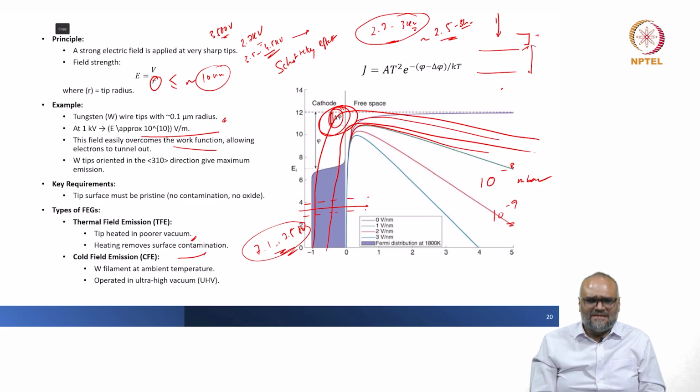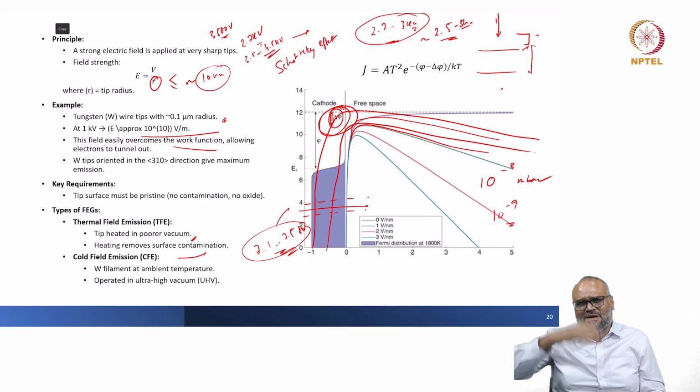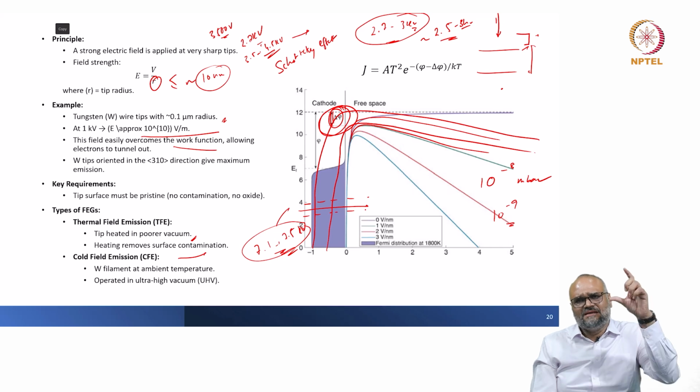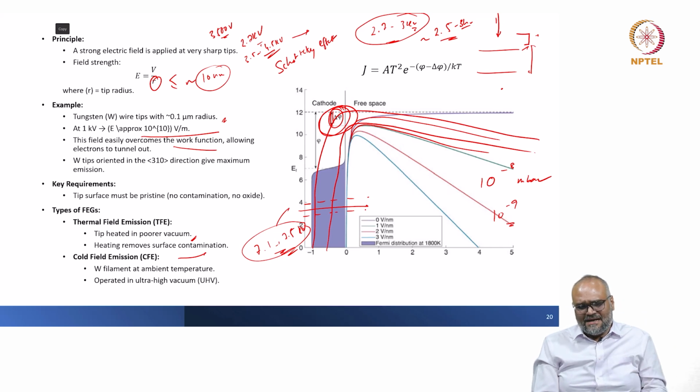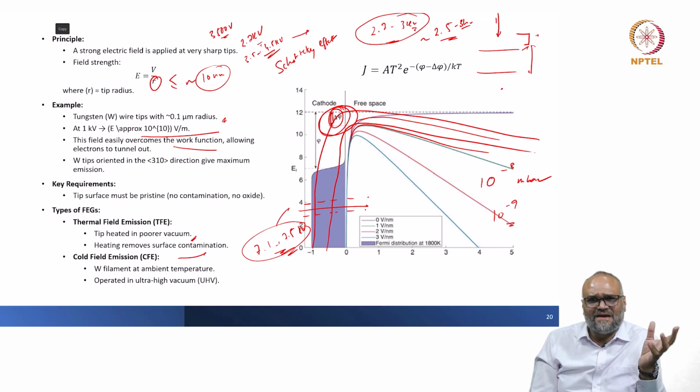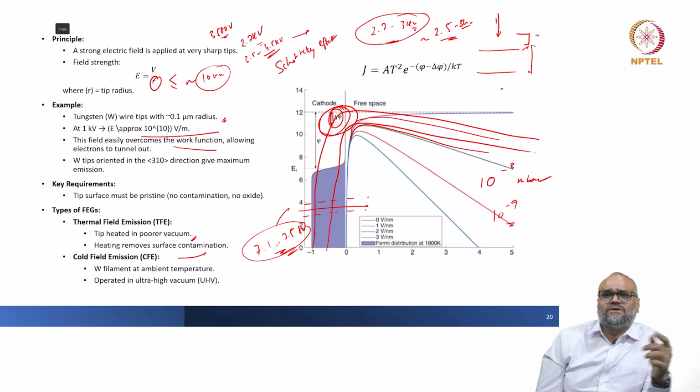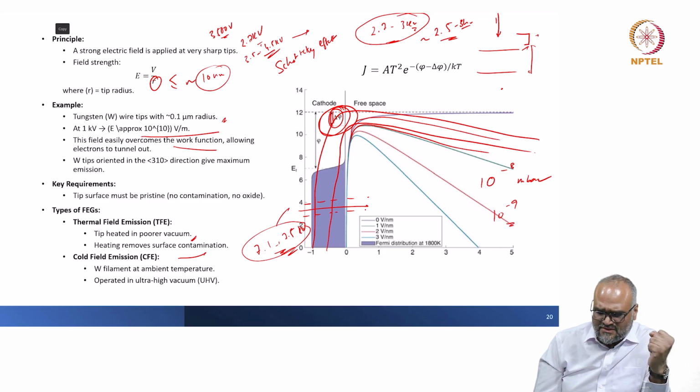What you do here is you go much beyond this 7.5 kV. You could go to a very high pulse over a very short span of 8 or 10 seconds, and you sharpen the filament tip in situ within the FEG assembly, and you can redo the emission and imaging again within the microscope.